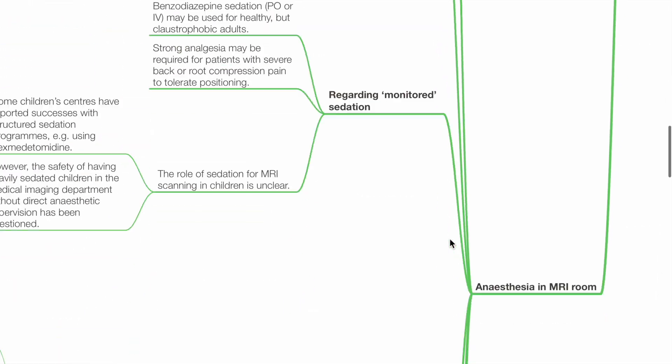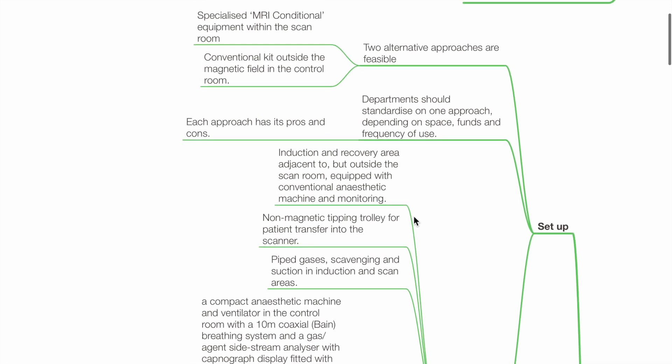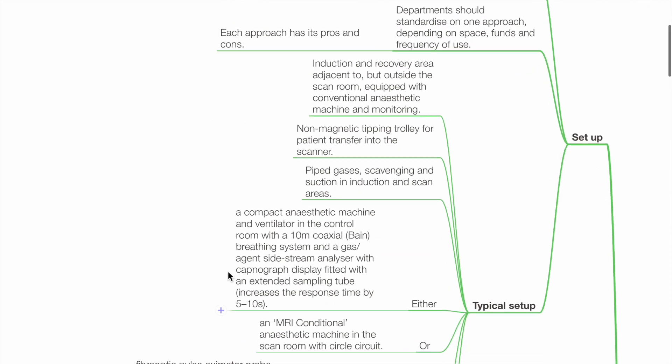Conduct of anaesthesia in the MRI room — setup: two alternative approaches are feasible. Specialized MRI-conditional equipment within the scan room, or conventional equipment outside the magnetic field in a control room. Departments should standardize one approach, depending on space, funds, and frequency of use. Each approach has its pros and cons.